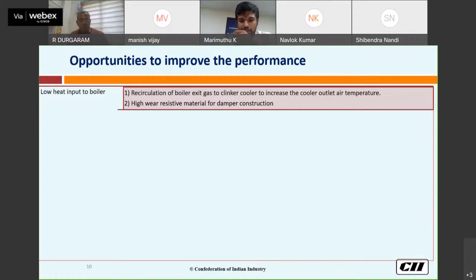Next, coming to the opportunities to improve the performance. First one, low heat input to the boiler. Suppose you are getting lower heat input than the design. What we need to do is recirculate boiler exit gas to the clinker cooler to increase the cooler outlet temperature. As Manish already discussed, recirculation is also helpful for increasing the heat input to the WHRS, which helps in power generation. Then next one is high wear resistant material damper construction. Because if the bypass happens, part of the gas will go to the stack and will not contribute to power generation.